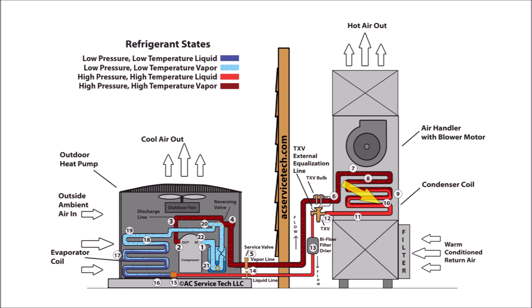Over at step ten, it turns into a complete liquid. After the refrigerant turns completely into a liquid at step ten, the liquid refrigerant then lowers in temperature over at step eleven — this is referred to as subcooling. This refrigerant is still considered high pressure, high temperature refrigerant, but in this case it's just lowering in temperature as a liquid. At step twelve, the high pressure, high temperature, subcooled liquid refrigerant bypasses through the inactive metering device and remains unchanged.